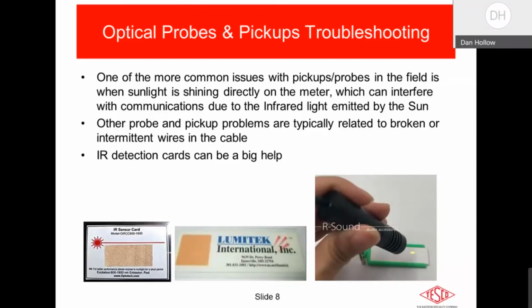If you can't communicate with it, then you know that it's something on the meter end. Maybe the meter has lost its mind and the firmware has gone off into la-la land. The optical port itself may have a problem with the phototransistor or the infrared LED on the meter. But at least this is a way of allowing you to determine: is it the meter, is it the optical probe, or is it the way I've configured the software to communicate with that meter? So it can be a very, very big help in troubleshooting to figure out where the problem lies.